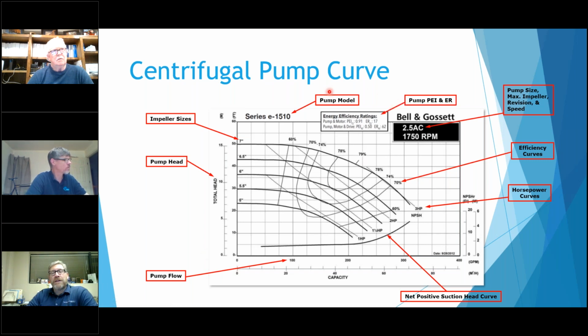This little box up here, this is something new. This just started to take effect in January of last year, January 2020. It's what they call the pump efficiency rating. The PEI is the pump efficiency index, and the ER is the efficiency rating. There are actually two different ratings. One, from the Department of Energy, is the PEI, the pump efficiency index.